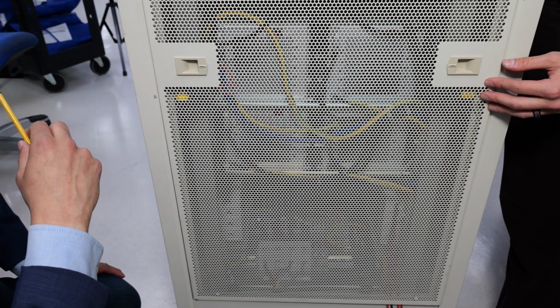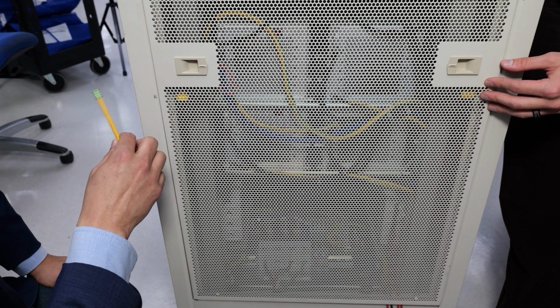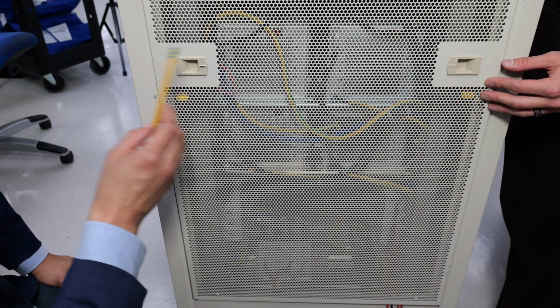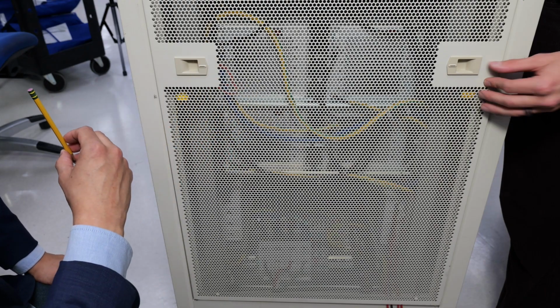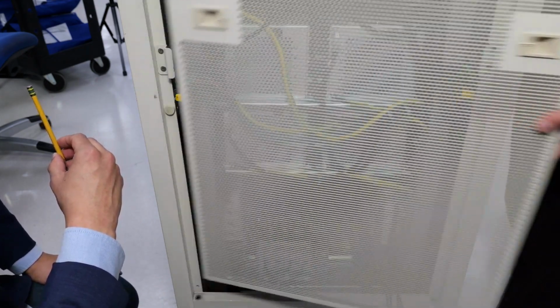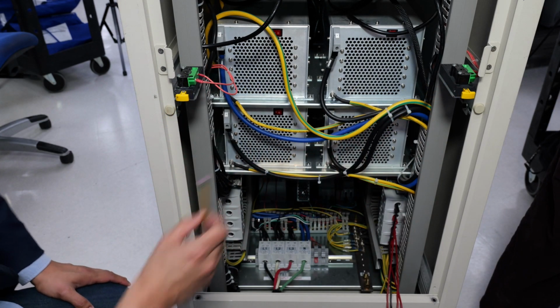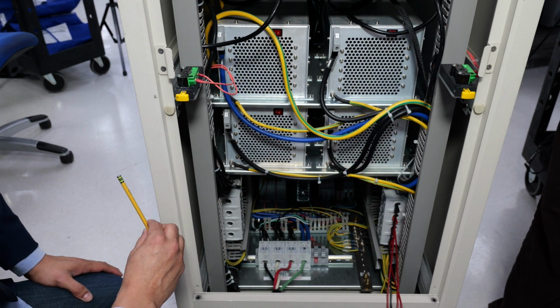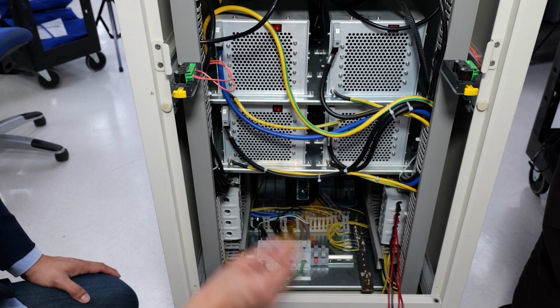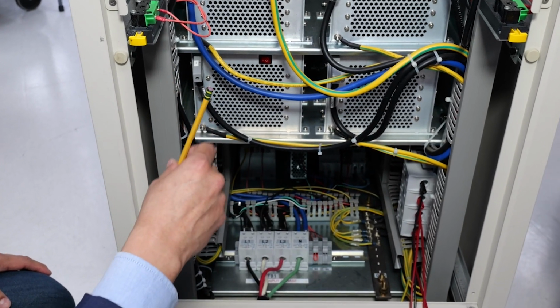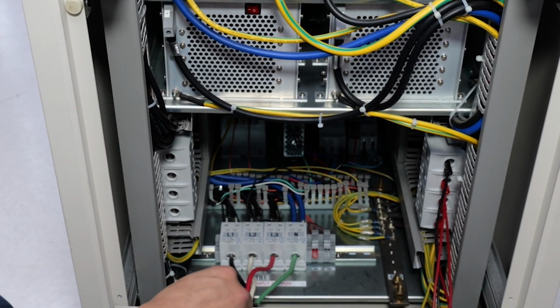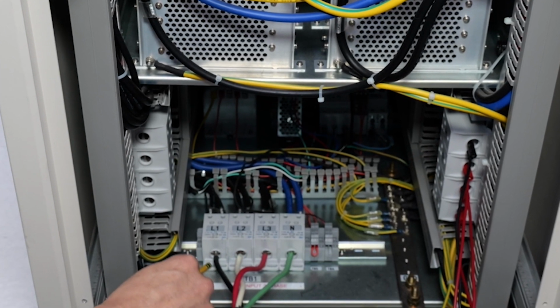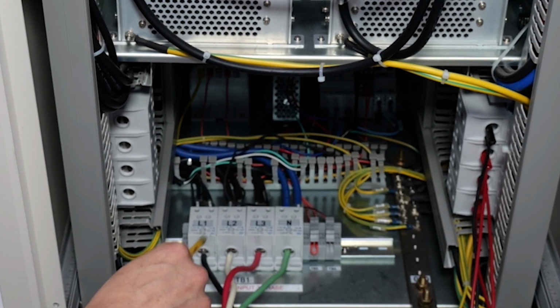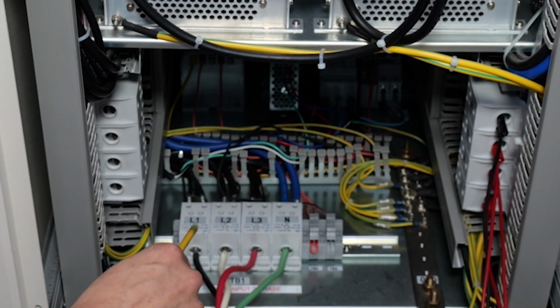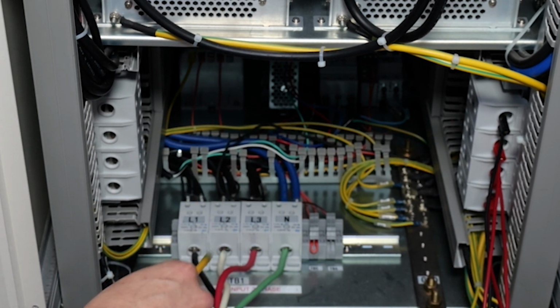So next we're gonna look at the rear panel of the three phase 75 amp analyzer. First things first, we're gonna pop the rear panel off. And as you see here, the rear panel has a few interlocks that will not enable use with the rear panel taken off. So you'll have to put that on before you start testing. Key things we're gonna look at down here: this is the 480 volts coming from our building mains that is actually powering on the analyzer.